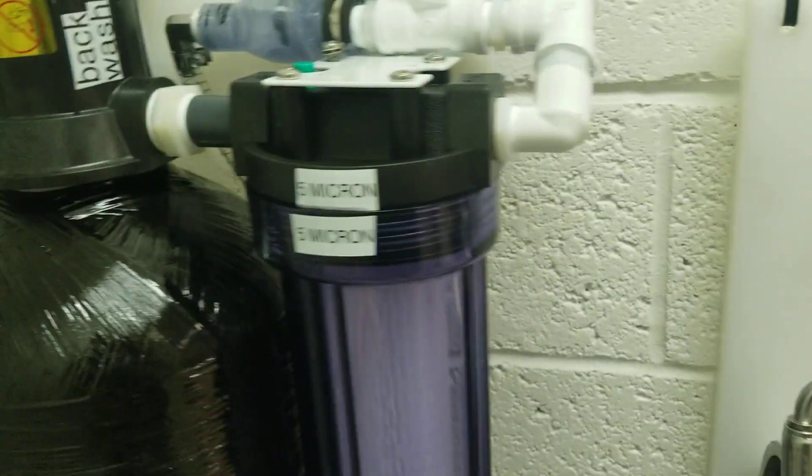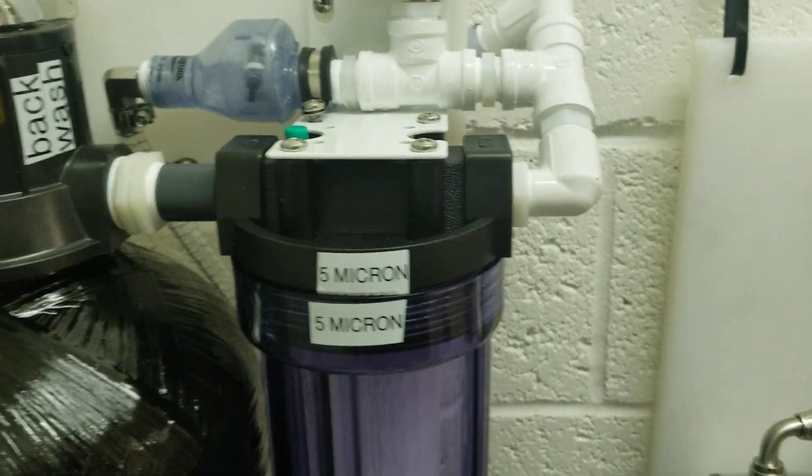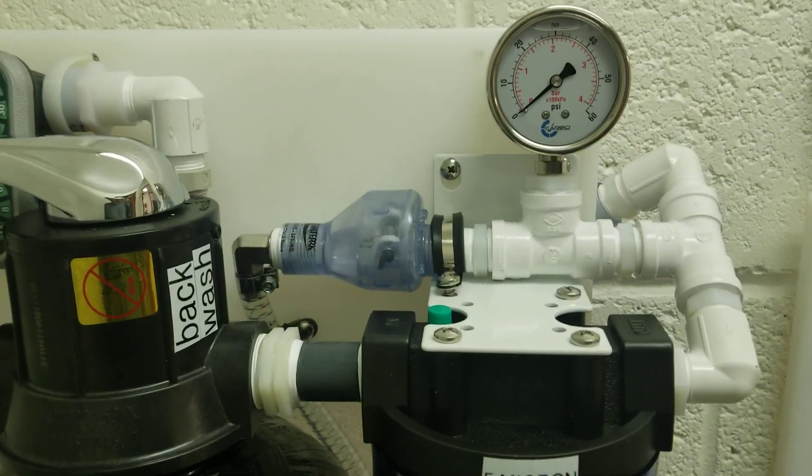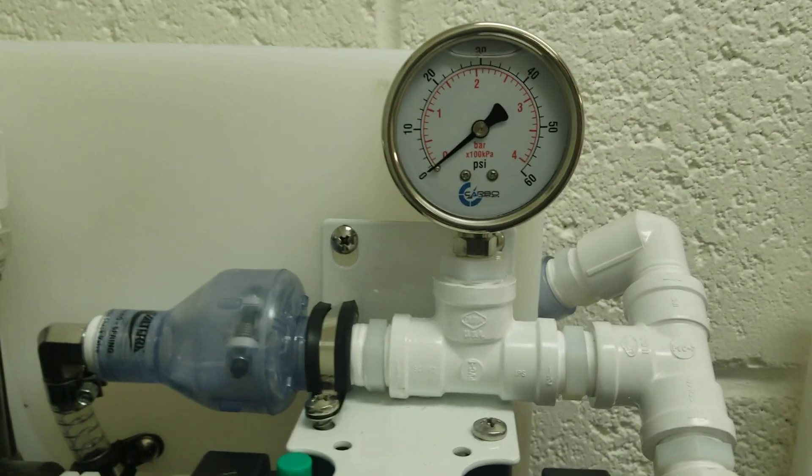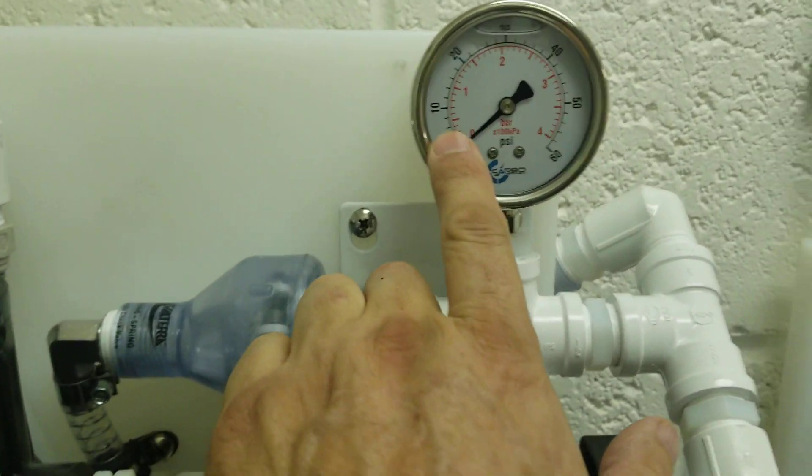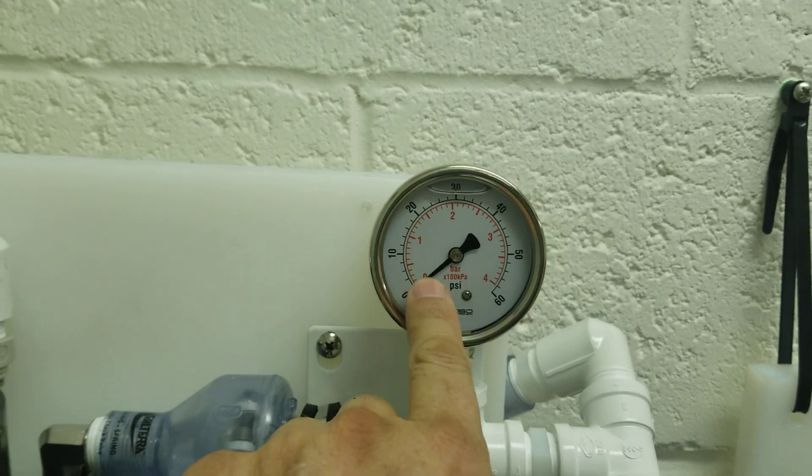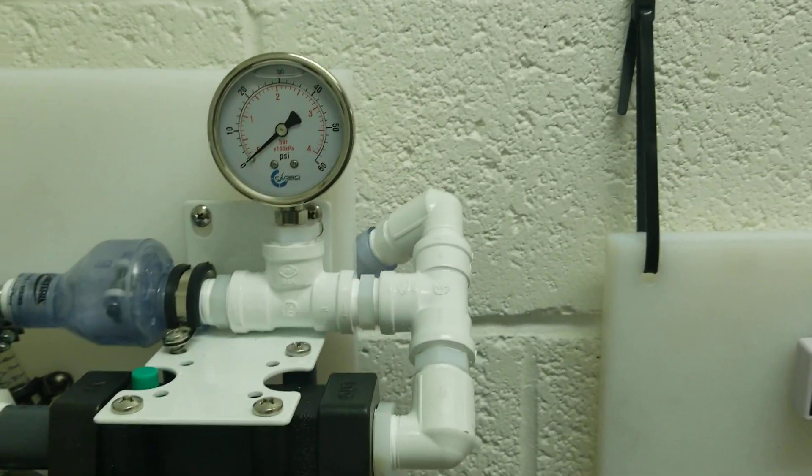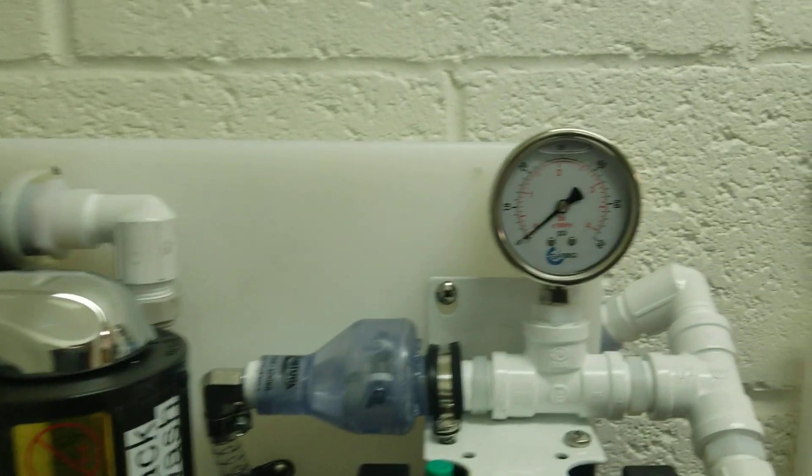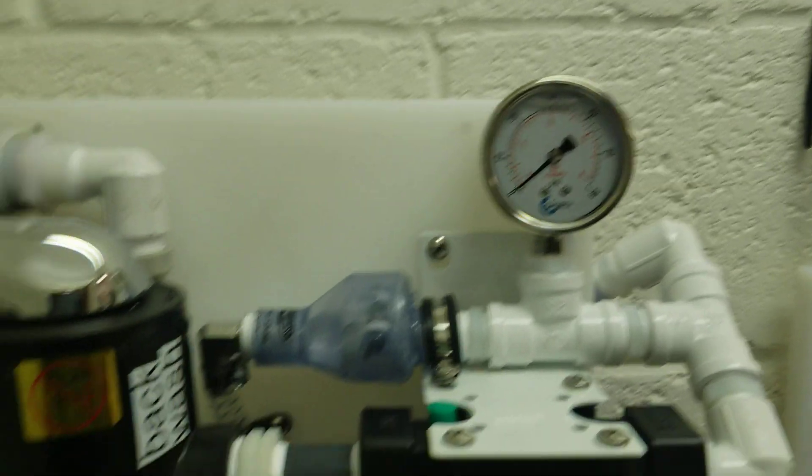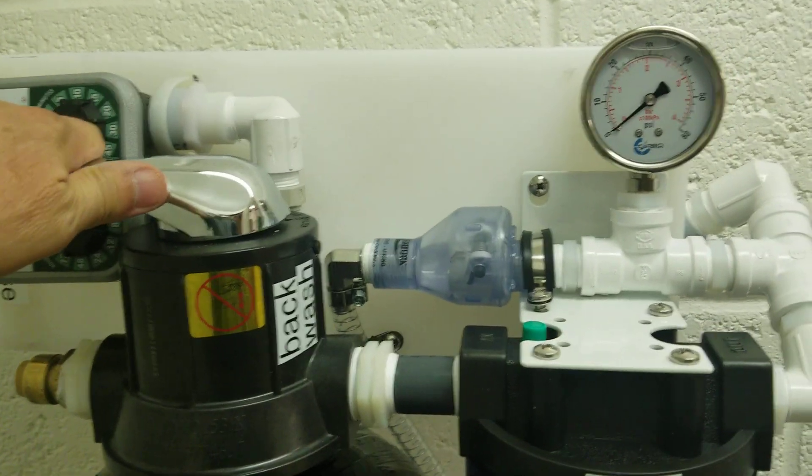And the second filter is for backup, just in case. Also here we have the pressure gauge that tells us whether the filters are flowing or they're plugged up. If you notice a pressure drop, then it's time to backwash the sand filter.